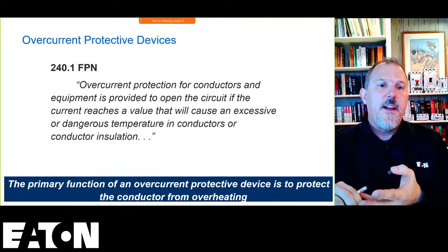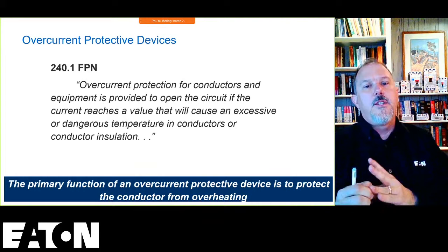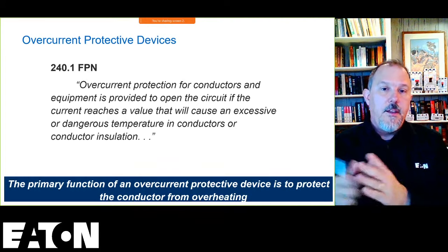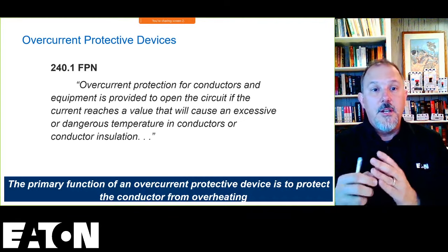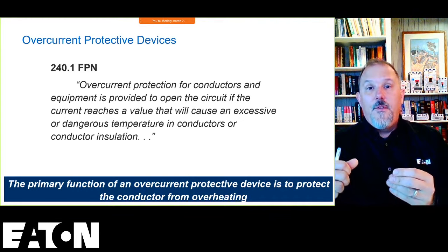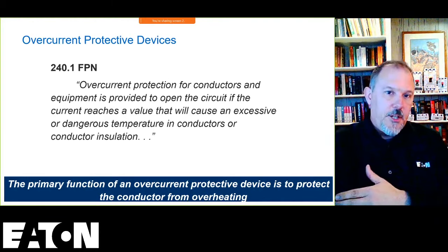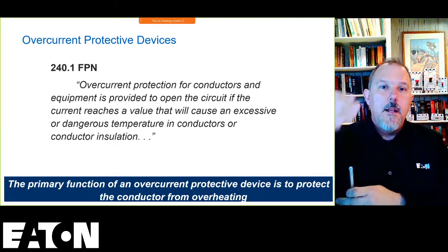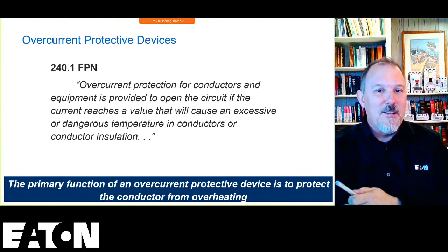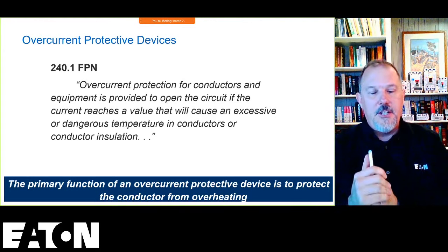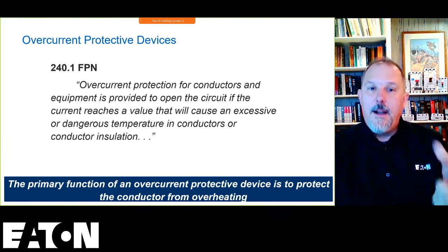Now, the fine print note in 240.1 tells us overcurrent protection for conductors and equipment is provided to open the circuit if the current reaches a value that will cause an excessive or dangerous temperature in conductors or conductor insulation. So for short duration overloads or long duration overloads, you can have an overload for quite a long period of time on a conductor before you get into damaging the insulation. It's all about current and time, how much current you're going to permit for how much time.